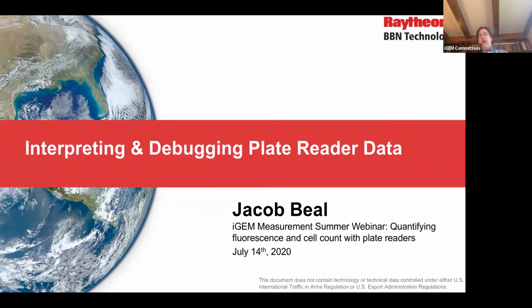On the measurement page, we have recommendations for the wavelengths to use for each of these. For fluorescein, my preferred numbers are excitation at 488 nanometers and emission at 530, a bandpass filter that's centered at 530 nanometers and is 30 nanometers wide. Like I said, these numbers are up on the site.